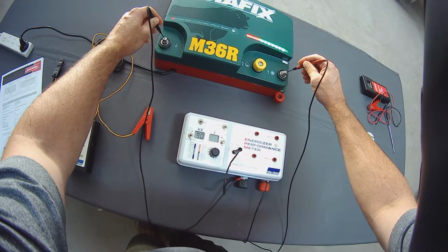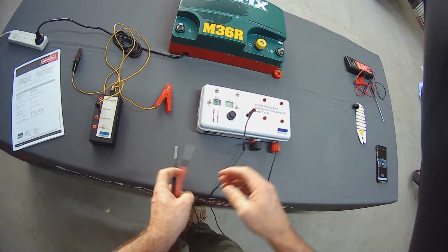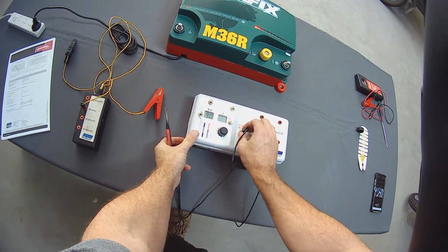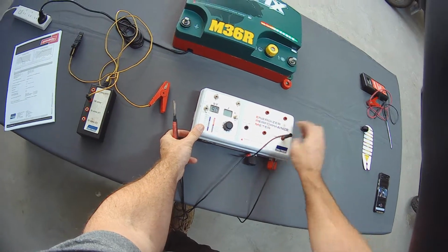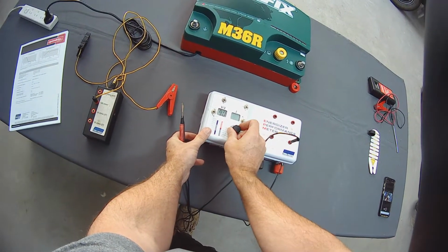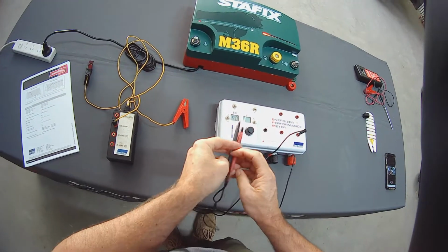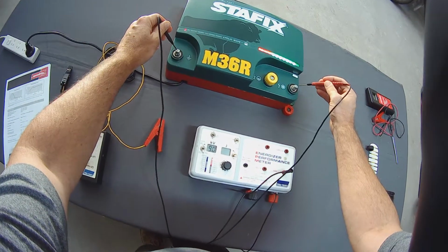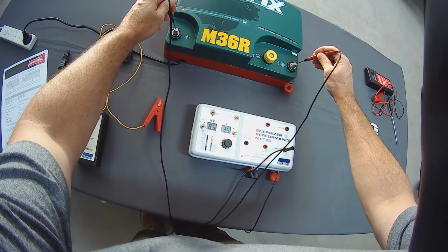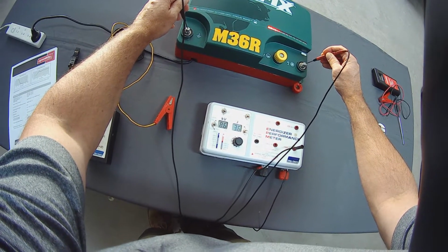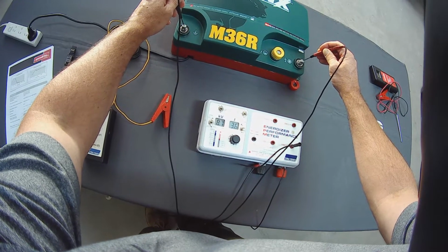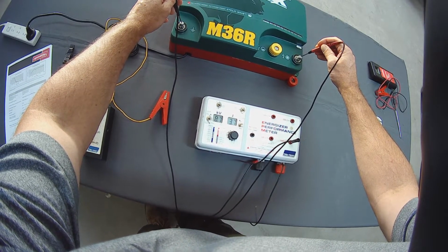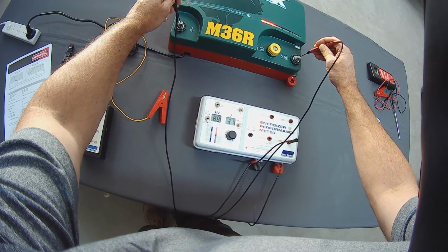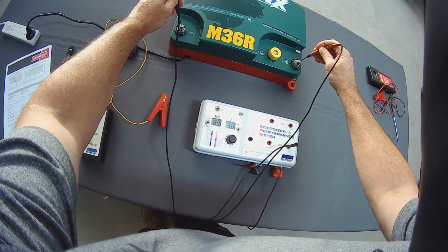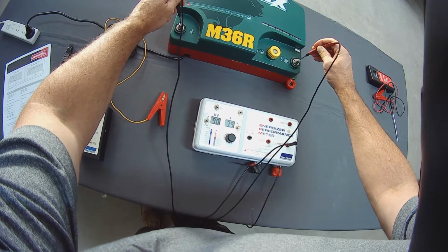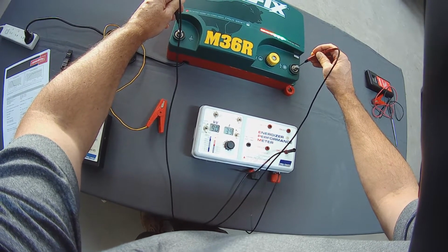If we then apply load to the unit, so if we go to 1000 ohms, that goes in the 1000 ohms port, the dial goes to 1000 ohms, probes on the terminals once again. You can see our voltage has dropped to 8.6. We're now producing 3.7 joules, 8.8, 8.9 kilovolts, 9 kilovolts, and we're just under 4 joules.